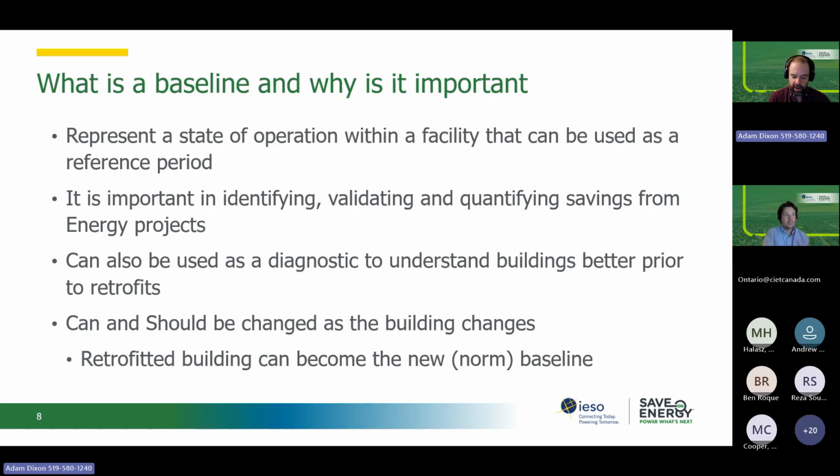So now you had a building with old lights in it, you put new lighting in there. Now that new lighting condition is the new normal in the building, and we can move our baseline forward. That's our new baseline period to compare to. So on a continual improvement model, any future projects are then compared to that condition, so you're not essentially double counting savings there.